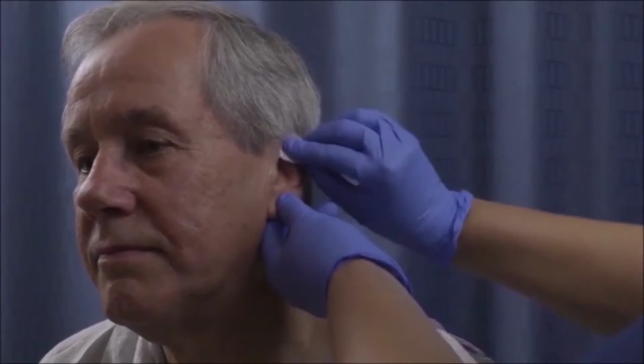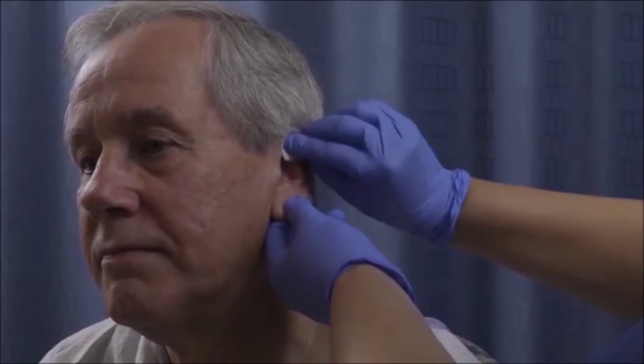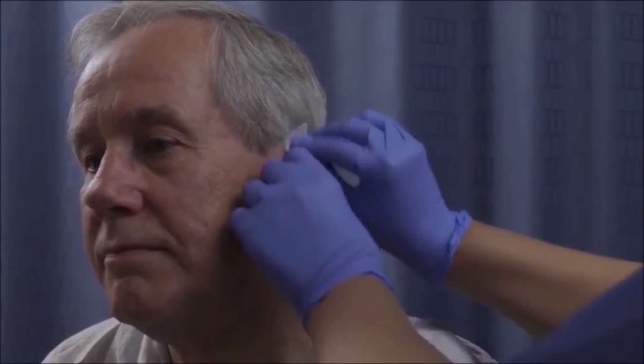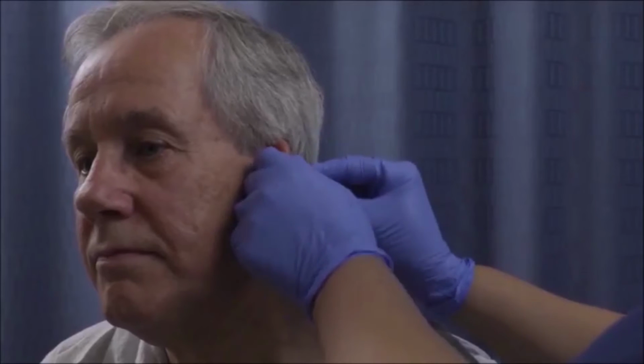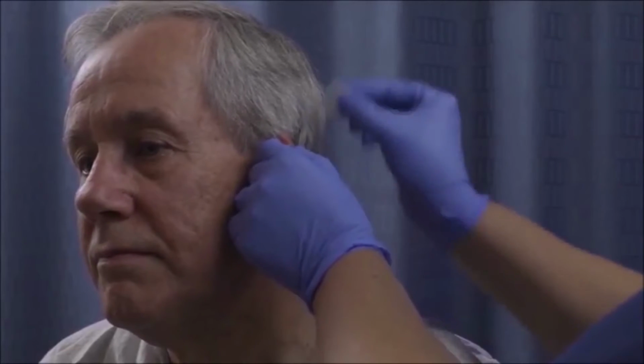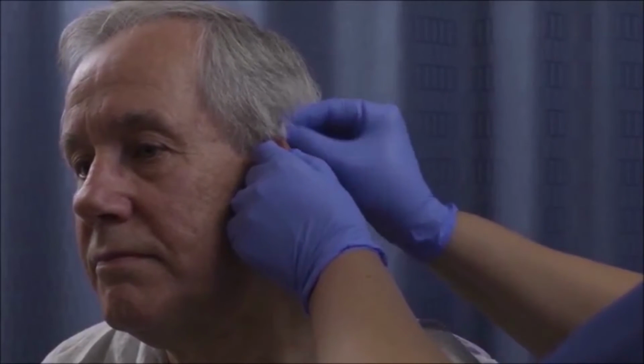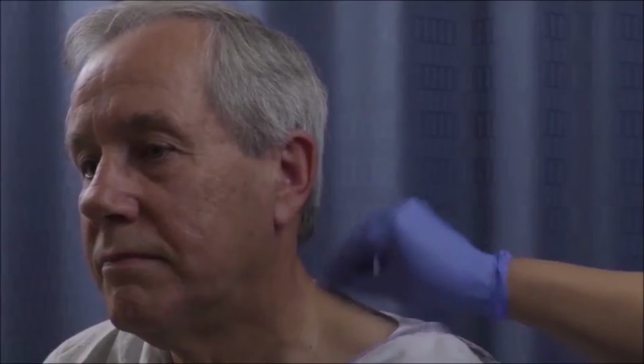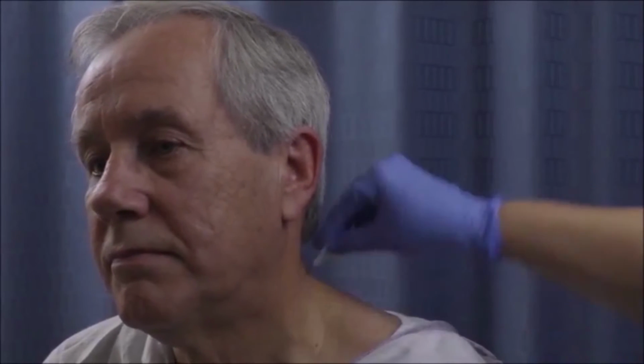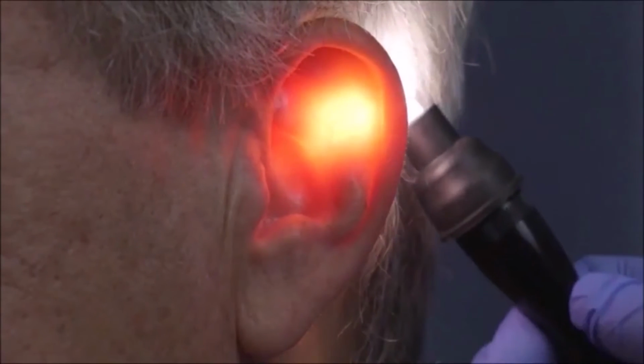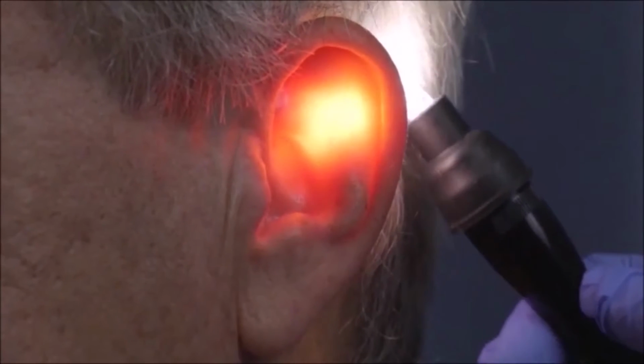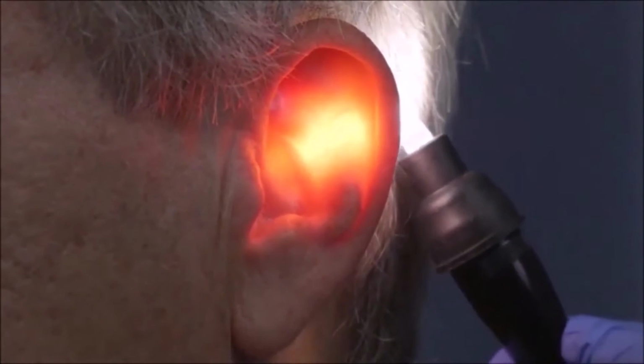Prepare the patient for installation of the Stivax device by cleaning the upper area of the patient's ear with the alcohol swab. Be sure to clean both sides of the ear, in the puncture area and behind the ear where the fixation plasters will adhere. Also clean a large area of the patient's shoulder on the same side as the ear that's being prepped for device installation.